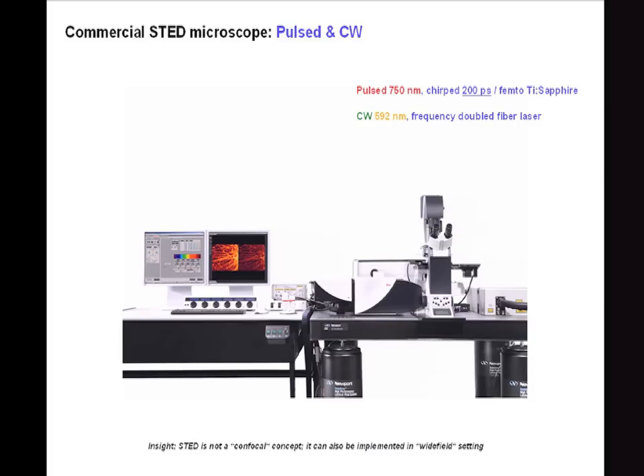You can easily add STED to any standard confocal microscope. This is a standard confocal microscope, and what is added here is a second beam of light that is shaped into a donut by applying a helical phase ramp, and then you just scan the beams — jointly the excitation beam and the STED beam — and you get the higher spatial resolution.